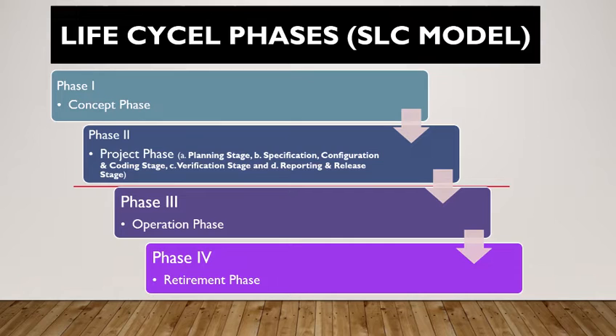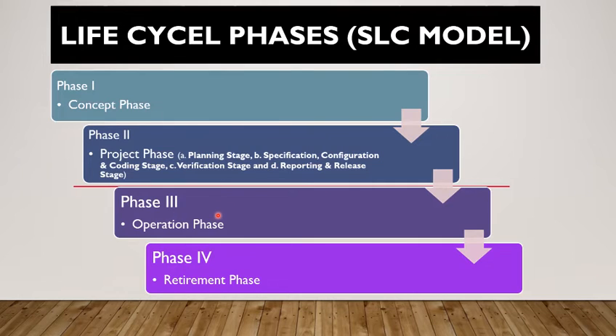Phase 1 is called the concept phase. Phase 2 is called the project phase, and this project phase is further divided into 4 different stages: planning stage, specification configuration stage, verification stage, and reporting and release stage. Phase 3 is called the operation phase, and phase 4 is called the retirement or decommissioning phase.